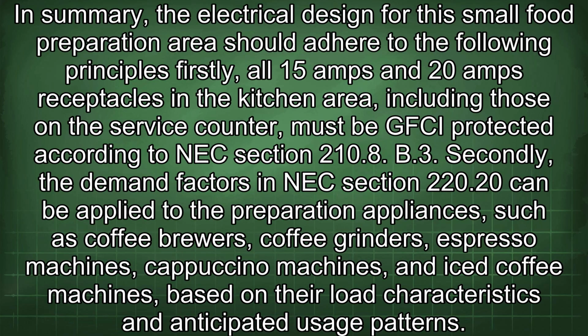In summary, the electrical design for the small food preparation area should adhere to the following principles. Firstly, all 15 amp and 20 amp receptacles in the kitchen area, including those on the service counter, must be GFCI protected according to NEC section 210.8(B)(3). Secondly, the demand factors in NEC section 220.20 can be applied to the preparation appliances such as coffee brewers, coffee grinders, espresso machines, cappuccino machines, and iced coffee machines, based on their load characteristics and anticipated usage patterns.